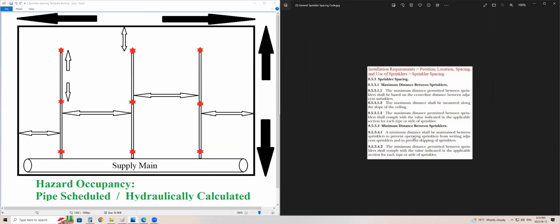What it means by wetting adjacent sprinklers is they want to prevent what's called cold soldering. And I think we've all heard at this point that the minimum distance for standard spray upright and pendants is 6 feet minimum, unless there is something to obstruct the discharge. So once we get into obstructions, that's a whole different cat.